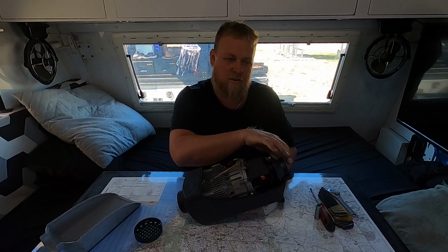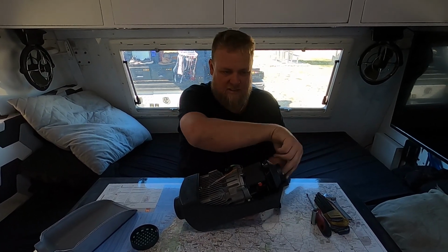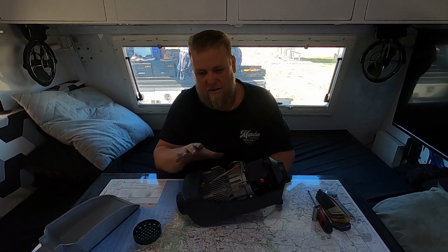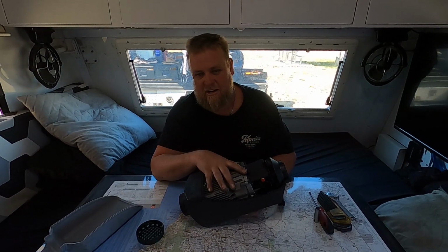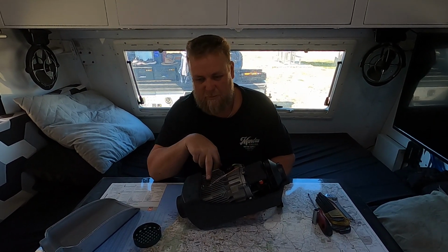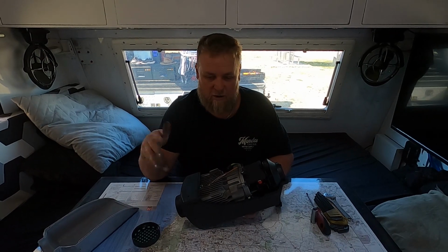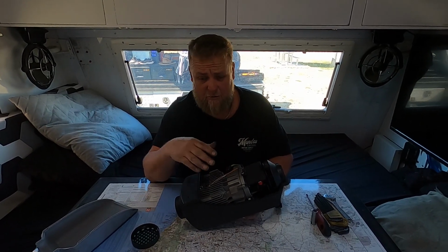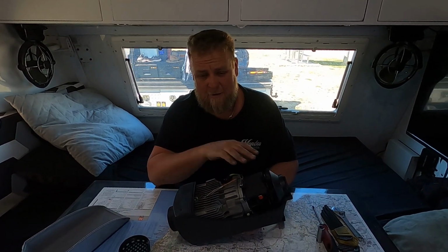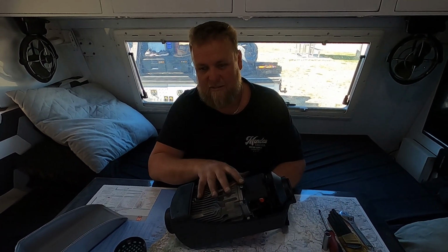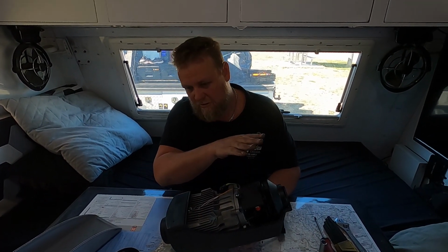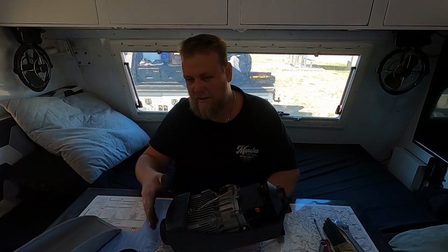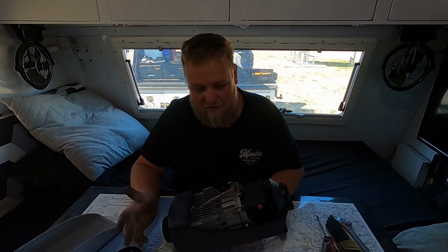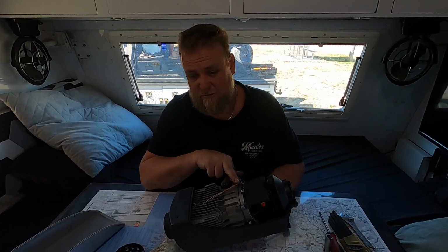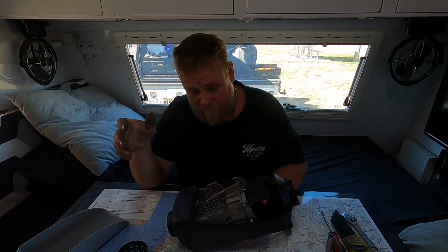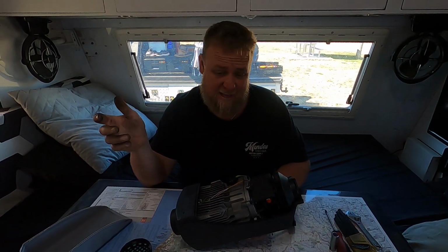So the air has actually got two purposes. It sucks in here, blows out here. Purpose one is to keep this heat exchanger at an acceptable temperature, which is measured by that temp sensor - which is why if it's not working, it throws an error code, because your computer doesn't actually know how hot the unit is. Purpose two is that the air blowing over it is what's heating your caravan. So like I say, if that gasket's good, it's impossible to get fumes. It's literally as simple as that.